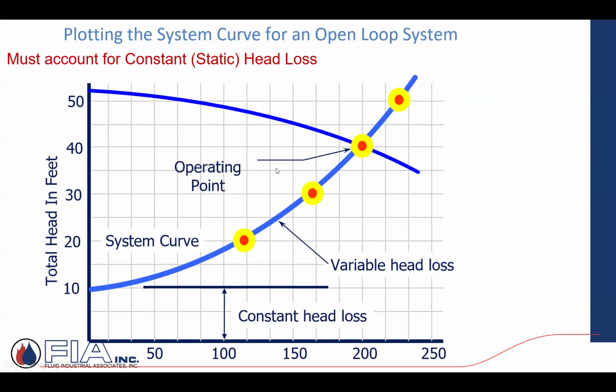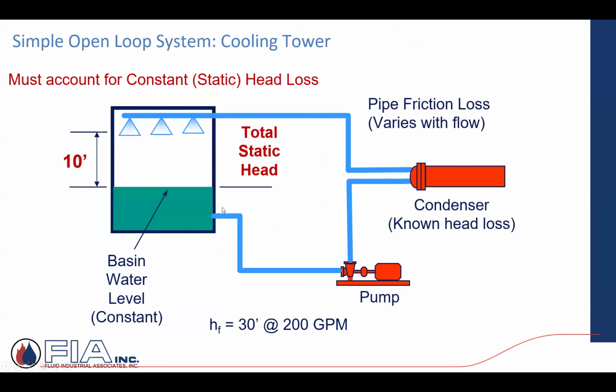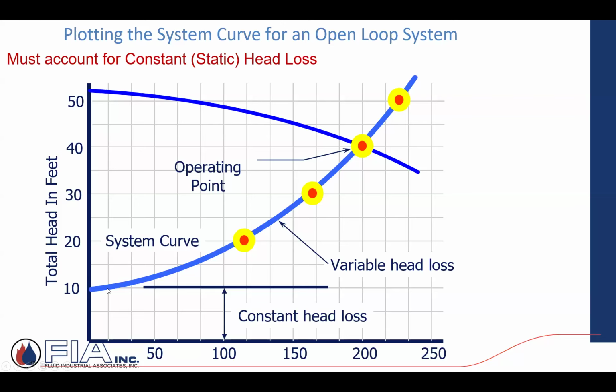So if I was to build a system curve for that set of conditions in this open system, I'm not going from 0. I have a built-in constant 10 feet of pressure differential that pump has to develop to overcome that vertical lift to get that water to that high point for that cooling tower. The variable will be, as I change the flow, the pressure drop in the piping, through the condenser, through the piping, that will change. Given the pipe size doesn't change, as you reduce the flow, you reduce the pressure drop. But that 10 feet never goes away. So when I build that curve, I always have that constant.